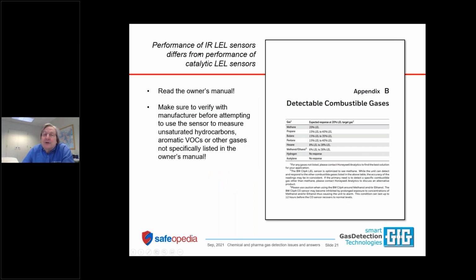When we're talking about the IR-LEL sensors, especially the miniaturized IR-LEL sensors, make sure that you actually read the owner's manual. When you go to the certification agency like UL or CSA, they are going to insist that you add certain warnings, and they're not going to give you the certification until they finally sign off on the owner's manual. That's part of the audited material. So generally speaking, you can trust it. You may not always be able to trust what my friends and colleagues among the professional salesman community say, I wish you could, but just in case, have a look at the owner's manual. The owner's manual you can trust.